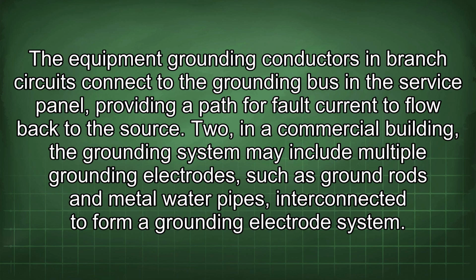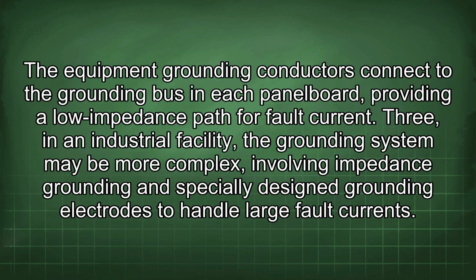2. In a commercial building, the grounding system may include multiple grounding electrodes, such as ground rods and metal water pipes, interconnected to form a grounding electrode system. The equipment grounding conductors connect to the grounding bus in each panel board, providing a low impedance path for fault current. 3. In an industrial facility, the grounding system may be more complex, involving impedance grounding and specially designed grounding electrodes to handle large fault currents.